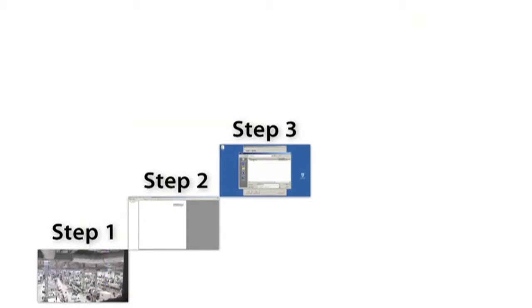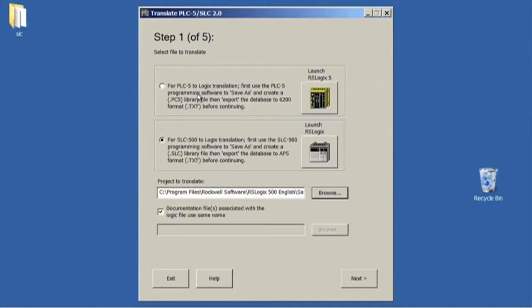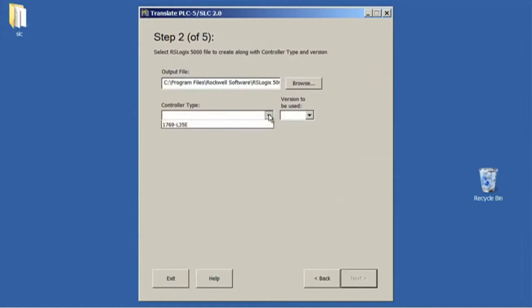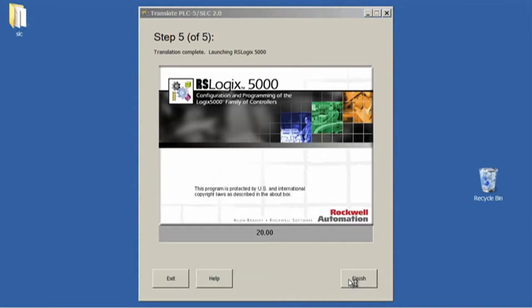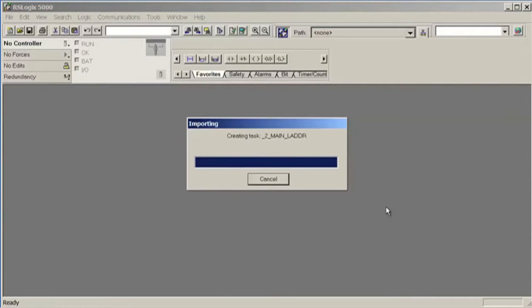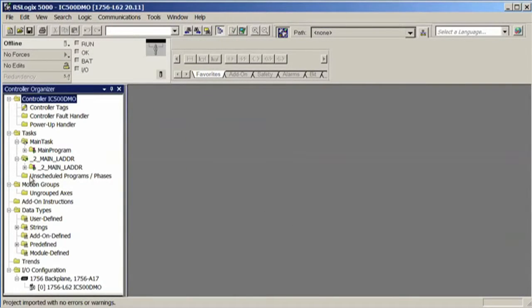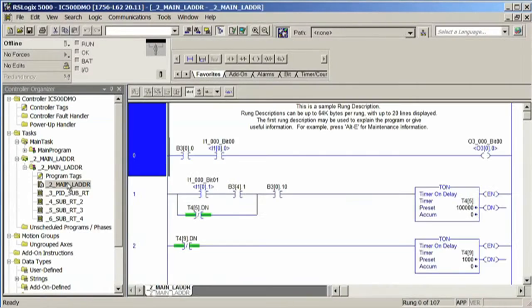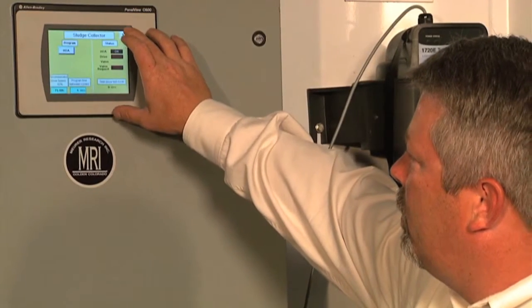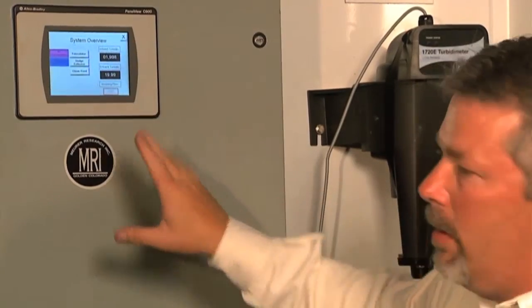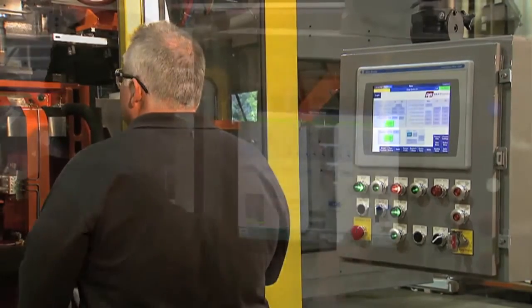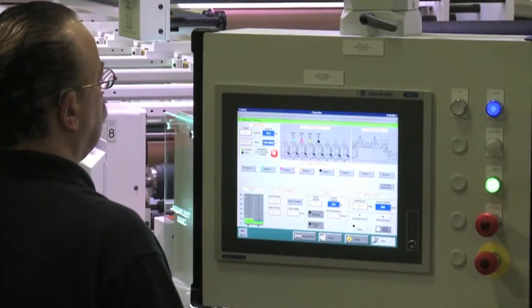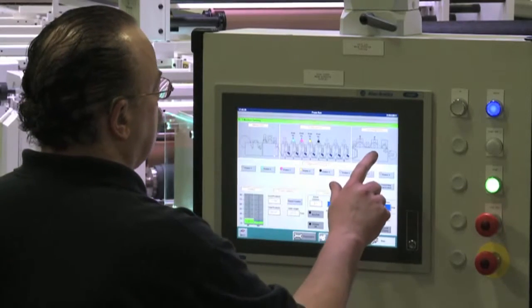Step 3. Save time and engineering resources by using the embedded conversion utilities for both PLC and HMI applications. RSLogix 5000 design and configuration software allows you to convert your existing RSLogix 500 program to RSLogix 5000 code. Graphic conversion utilities are available for PanelView Enhanced, PanelView Standard, and non-Rockwell Automation HMIs. Using these tools makes the conversion much more cost-effective, as well as providing greater flexibility regarding the final product.